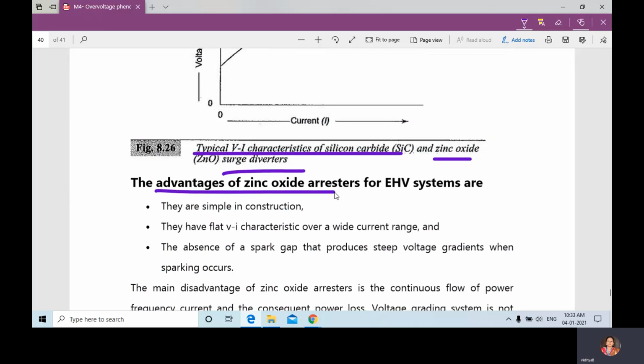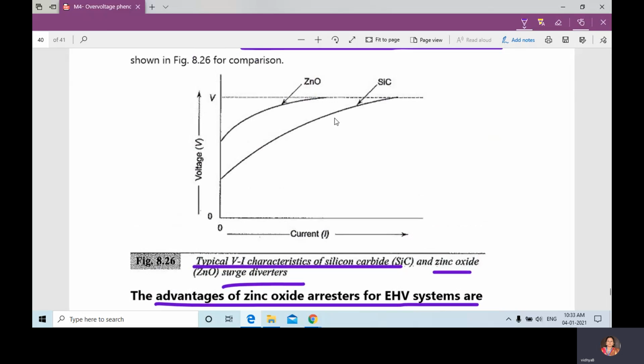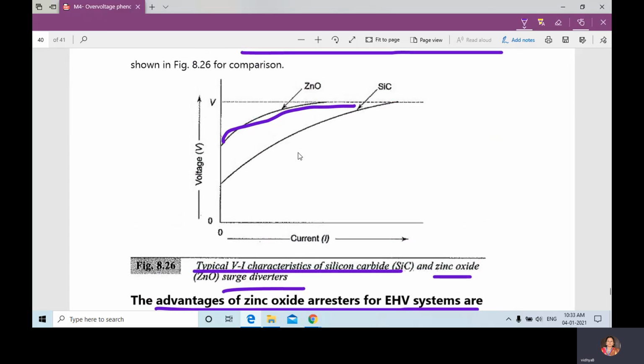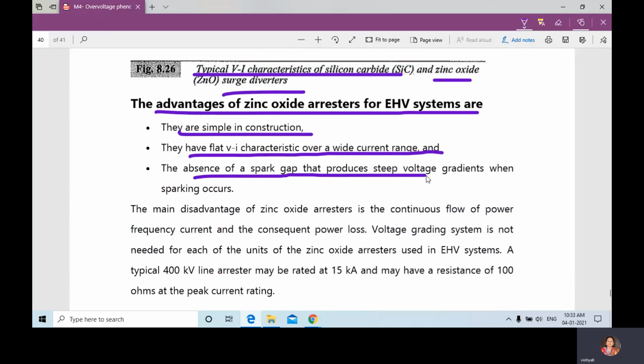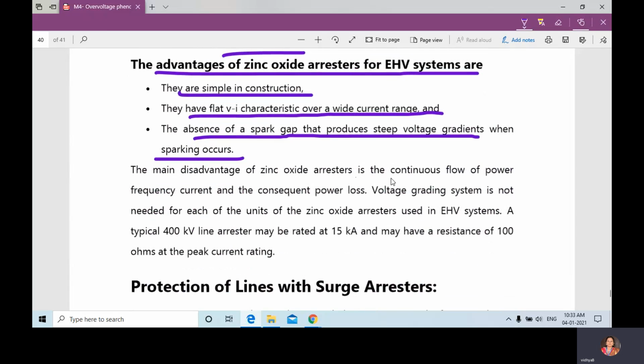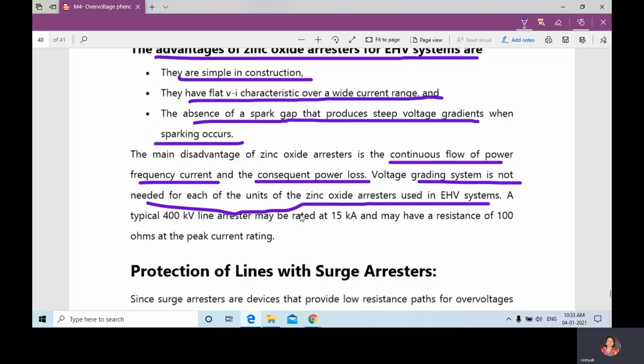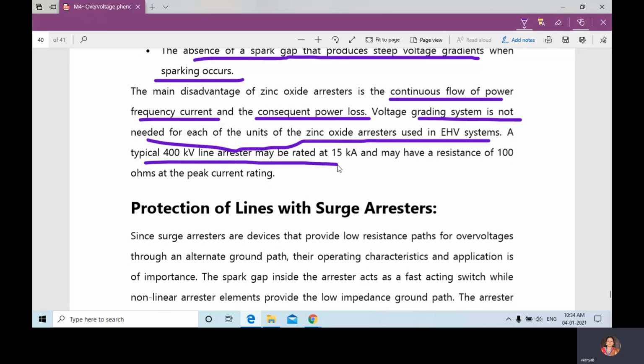The advantages of zinc oxide arrestor for extra high voltage systems are that they are simple in construction and have flat VI characteristics over a wide current range, and you can observe this for zinc oxide. There is also an absence of spark gap that produces steep voltage gradients when sparking occurs. The main disadvantage of zinc oxide arrestor is the continuous flow of power frequency current and the consequent power loss. A voltage grading system is not needed for each of the units of zinc oxide arrestor used in the extra high voltage system. A typical 400 kV line arrestor may be rated at 15 kA and may have a resistance of 100 ohms at the peak current rating.